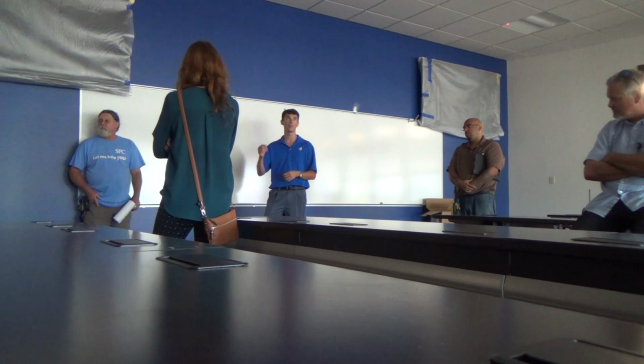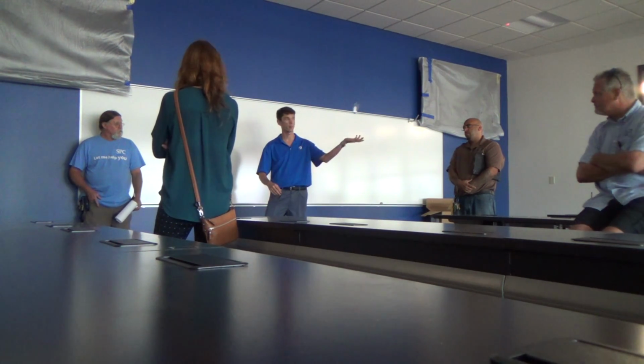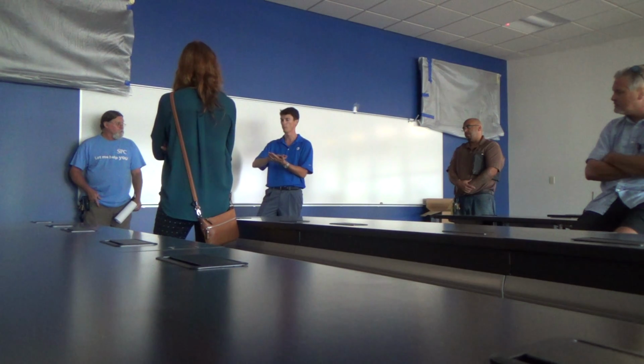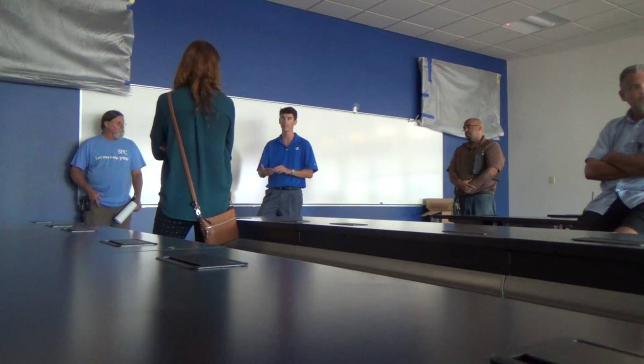And what would happen if you, say, blew a power pack, you got a surge come in somehow, let's just say a power pack blows? So if it's dead, the network won't be able to see it anymore. And when you go into SensorView, it'll pop up with something that says, I could see this device before and I can't now. So that's your opportunity to say, okay, well that's my bad device, and now we just need to go find it, swap it out, and when you swap it out, you go back into SensorView. And that's what I would do, or we can show you all how to do that also.